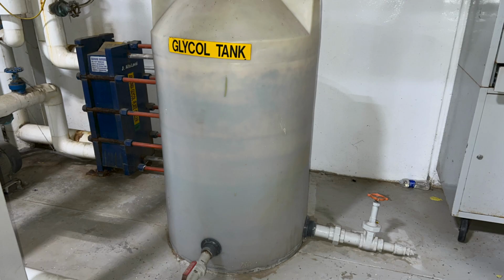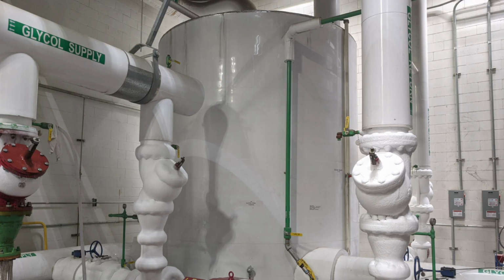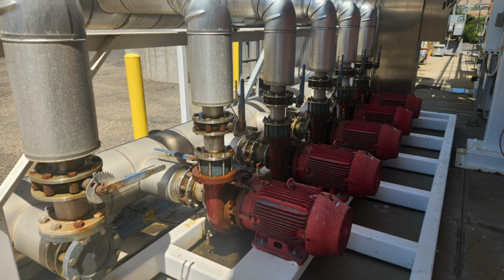Secondary coolants are fluids used to transfer heat in refrigeration systems by acting as an intermediary between the primary refrigerant and the area or substance being cooled. Unlike primary refrigerants, which undergo phase changes to absorb and reject heat, secondary coolants remain in the same phase, typically liquid, while carrying heat away from the cooled space.